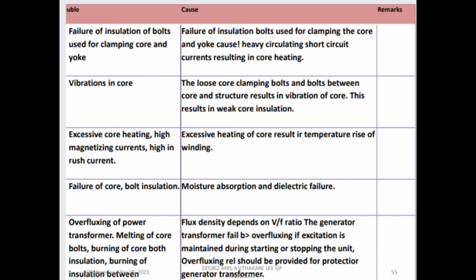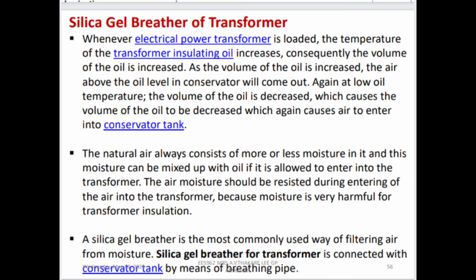So the cause is flux density depends on the V by F ratio. The generator transformer fails if V by F is higher, overfluxing, if excitation is maintained during starting or stopping the unit. Overfluxing relay should be provided for protection of the generator transformer. So the silica gel breather of transformer: silica gel is used to absorb the moisture when it is connected in the transformer.